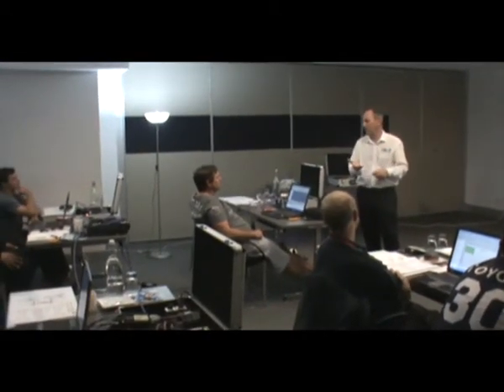So when you see this happening, what you really should do is look for common cause failures. You should say, the devices that have fallen off the bus, which you can tell from your analyzer, what's common to those devices? Maybe they're all on the same segment. Maybe they're all in the same cabinet, all on the same power supply. So you can answer that kind of question and home in on where the problem is.